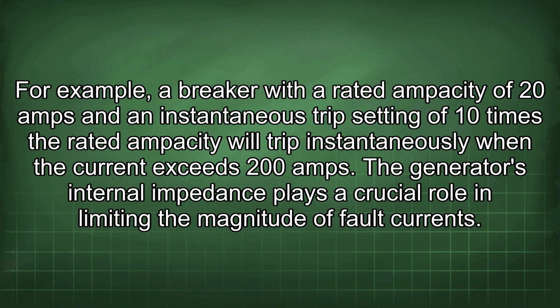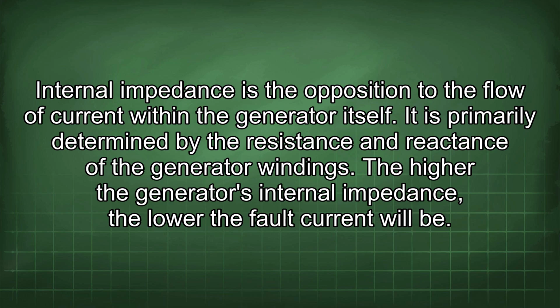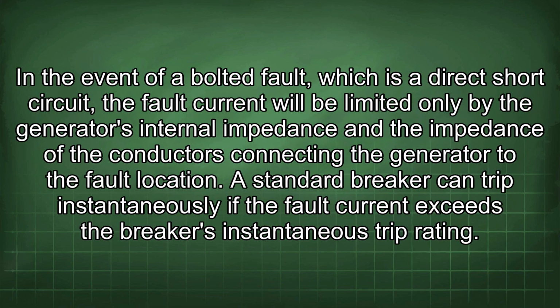The generator's internal impedance plays a crucial role in limiting the magnitude of fault currents. Internal impedance is the opposition to the flow of current within the generator itself. It is primarily determined by the resistance and reactance of the generator windings. The higher the generator's internal impedance, the lower the fault current will be. In the event of a bolted fault, which is a direct short circuit, the fault current will be limited only by the generator's internal impedance and the impedance of the conductors connecting the generator to the fault location.